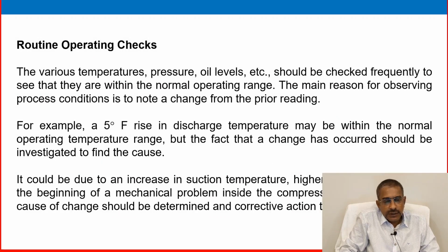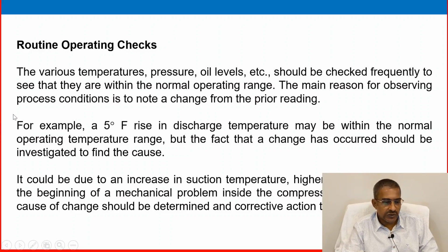Routine operating checks. After running the machine, operating checks are very important. Various temperatures, pressures, and oil levels should be checked frequently to see that they are within the normal operating range. The main reason for observing process conditions is to note a change from the prior reading. For example, a 5° Fahrenheit rise in discharge temperature may be within the normal operating temperature range, but the fact that the change has occurred should be investigated to find a cause. It could be due to an increase in suction temperature, higher compression ratio, or the beginning of a mechanical problem inside the compressor. In any event, the cause of the change should be determined and corrective action taken if necessary.